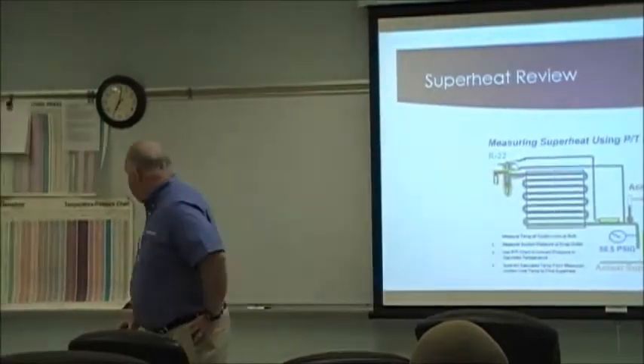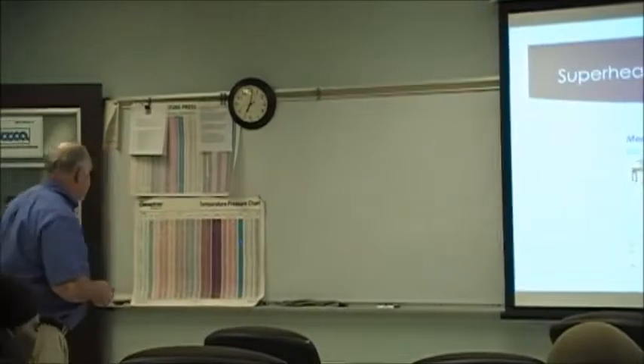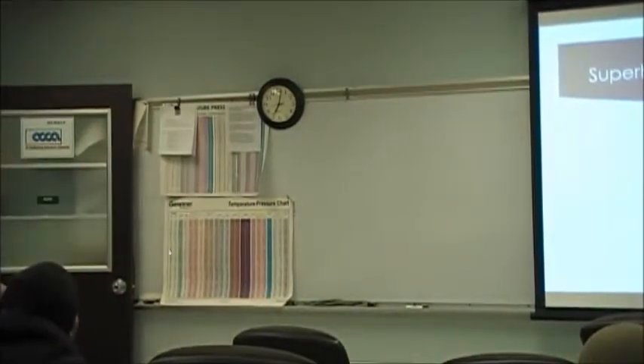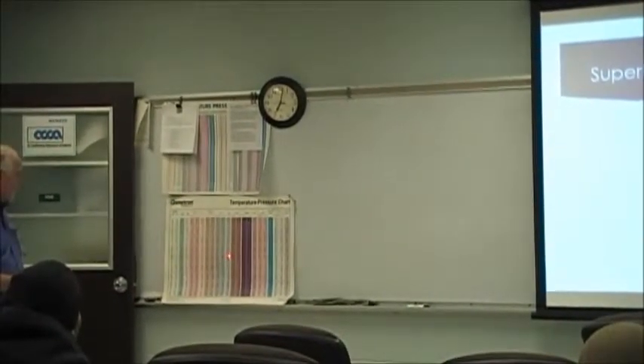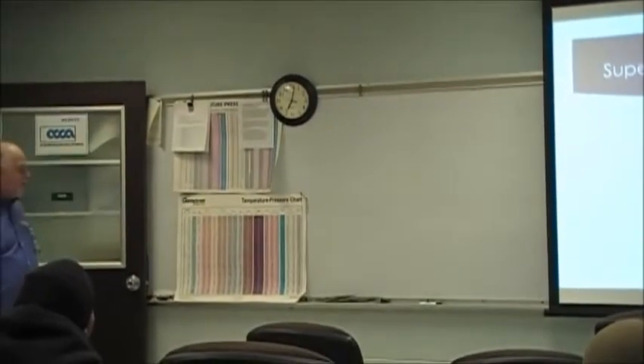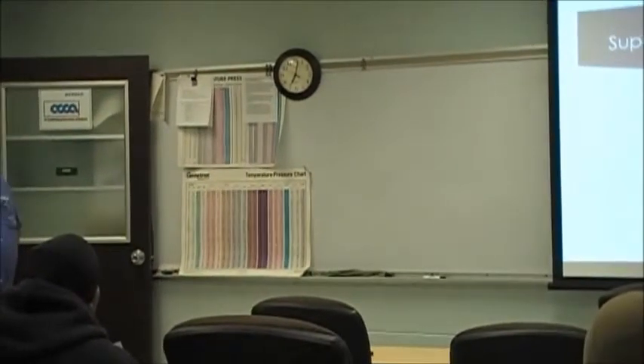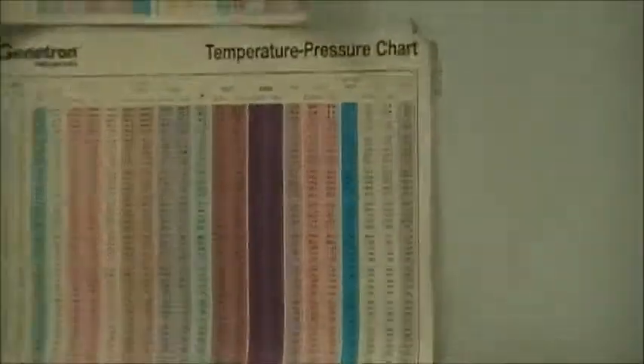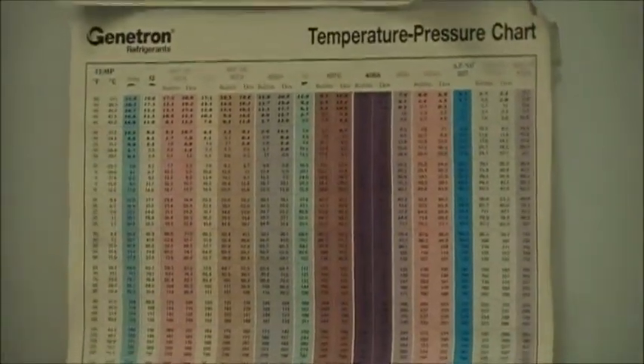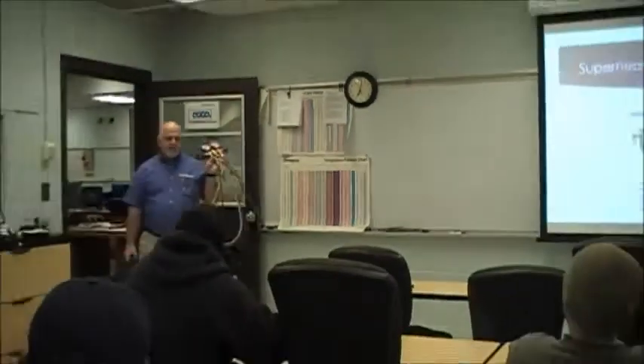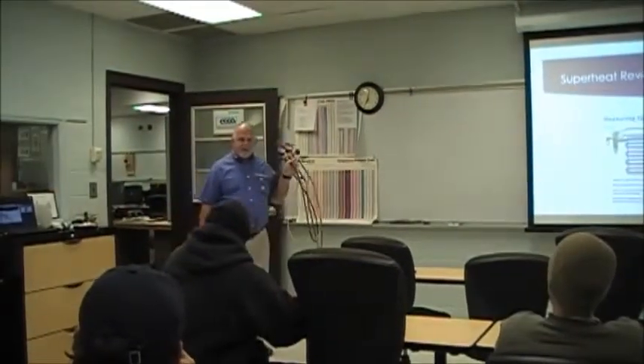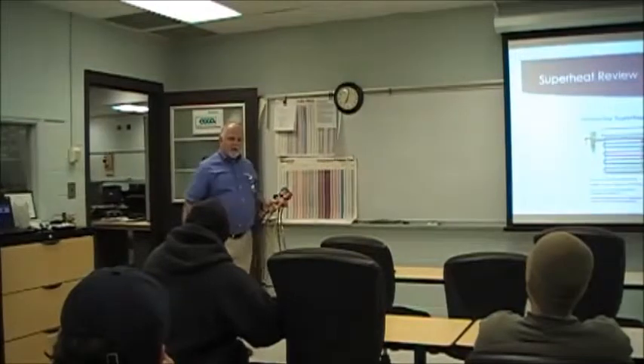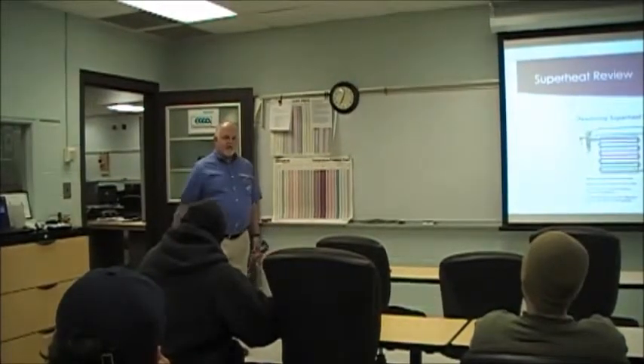Now, it says on this chart right here that for R22, at 40 degrees, 68.6 pounds is the pressure it will be at. I'm here to tell you that if I had a drum of R22 and I hooked this gauge to it right here, and that drum had been sitting, and I read the pressure off this gauge, I could tell you what the temperature was of that refrigerant.